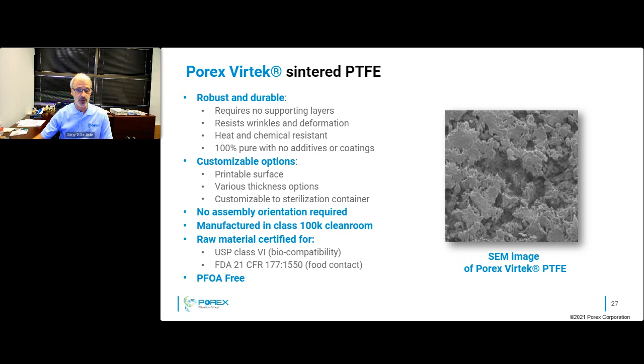It's customizable in the sense that the surface is printable. We can make it in various thicknesses. For sterilization containers, it comes in three thicknesses: 0.25 millimeters, 0.64 millimeters, and 1 millimeter thick. The thicker the material, the longer the life of the material. And it can be customized to your sterilization container. This is a common size. I think these are 190 millimeters, but they can be made in rectangles, they can be made in squares, they can be provided in strips, however else is needed for your application. There's no assembly orientation, so both sides are the same, so it can be inserted either way. It doesn't matter. The product's all manufactured in a class 100,000 clean room, and all our materials are USP Class 6 biocompatible, and we do meet FDA requirements as well.